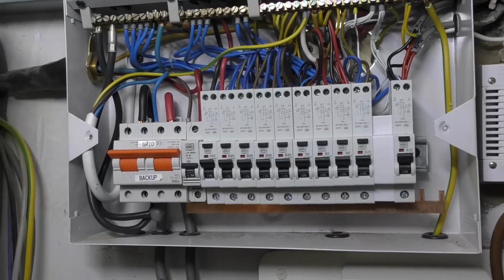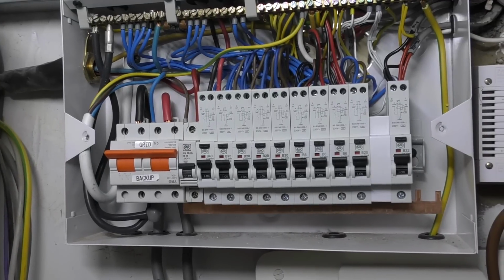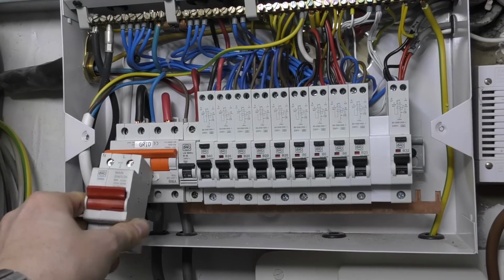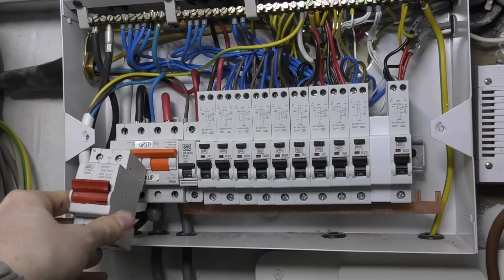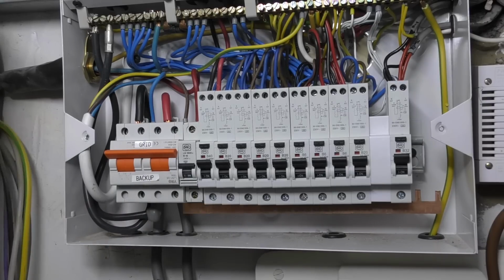And the nice thing, this is only a 4 unit wide switch, so compared to the original switch, this is only another 2 units wide, so it doesn't need a great deal of extra space to fit. I actually already had the space in there. I previously converted this from dual RCD into RCBO, so I already had the space for it, so that was just quite a nice solution. So it's a very simple solution. It's just really the inlet and that changeover switch, and that's all, so it's fairly minimal effort.